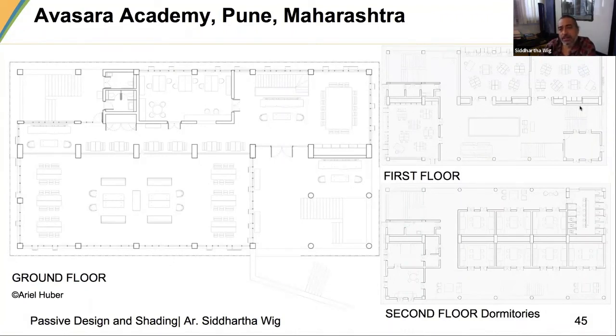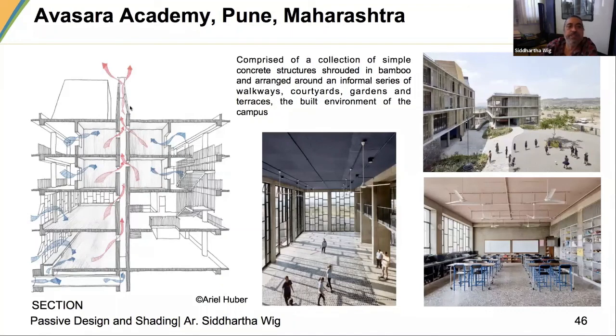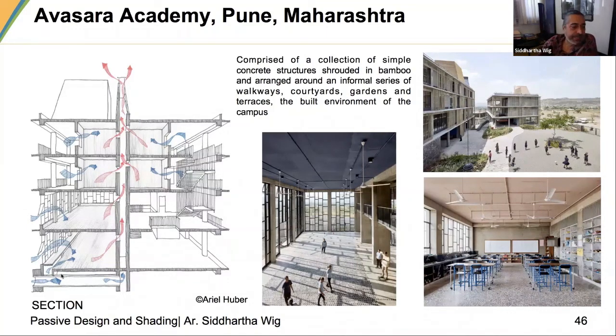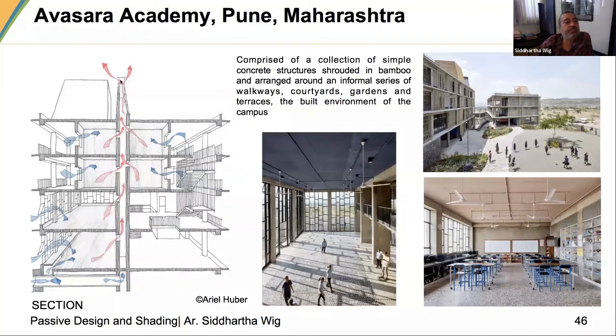The glazing is on all sides. Bamboo panels of three densities are used all around the building — to cover pipes, as protection from summer sun, and as a design aesthetic. In the middle of the plan on all floors there is a shaft used in an interesting way: a solar chimney at the center of the building, with large glazings on all sides and a lot of openness to allow cool air in. Large one-meter Hume pipes are put under the building to allow cool air to enter and cool under the floor.